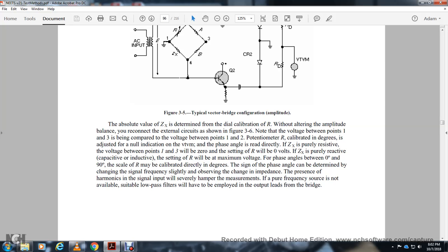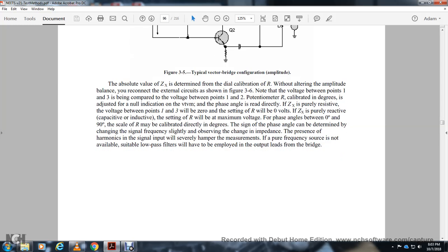The presence of harmonic signals at the input can severely hamper measurement accuracy. A pure frequency source is preferred; if not available, suitable low-pass filters should be employed at the output leads from the bridge.